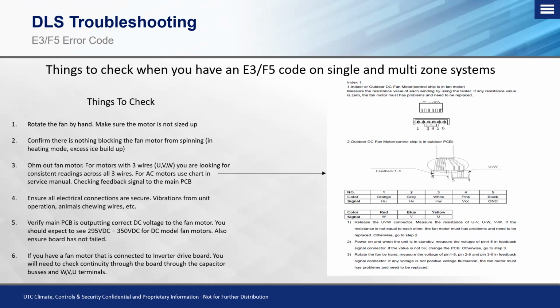The next thing that we want to check is that all the electrical connections are secure and tight. Situations such as vibrations from unit operation can work them loose, especially on the board, not so much with the Molex plugs, or the classic one, animals getting into the outdoor unit and making a nest in there. And of course, they're looking for material to make the nest. They start chewing through wires, and if they chew through the fan motor wire, when it's not calling, they're going to separate one of the legs, and it's not going to be able to run.